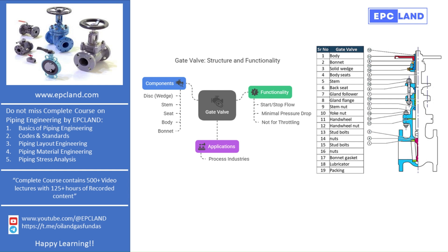Now let's briefly look at the parts of a gate valve. The main part is the disc, which is also called the wedge. This wedge is the part that moves up and down to block or allow flow. There's also a stem which connects the hand wheel or actuator to the disc. Turning the hand wheel raises or lowers the stem, which in turn moves the disc. The seat is the surface where the disc rests when the valve is closed. The body holds everything together and the bonnet is the cover on top of the valve where the stem moves in and out.